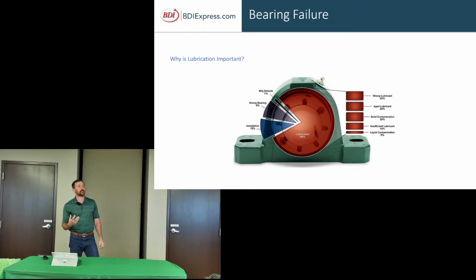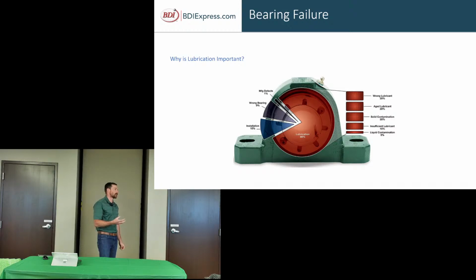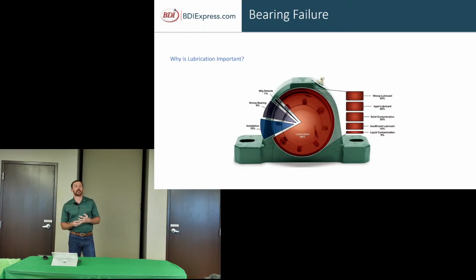Insufficient, so not having enough lubrication. This will go back to a chart further down. Depending on the bearing size, it's going to take more grease than a smaller bearing. And liquid contamination. Liquid is going to get in there depending on if you're outside in the snow and you guys get dumped on up in Wyoming, or if you're up in the mountains of Colorado, water can get in there, and that's going to cause corrosion. You want to stay away from that.